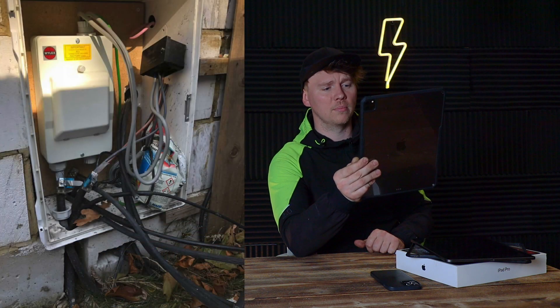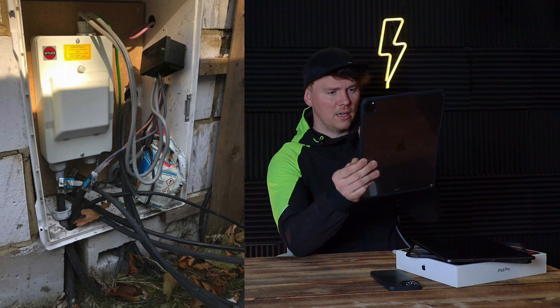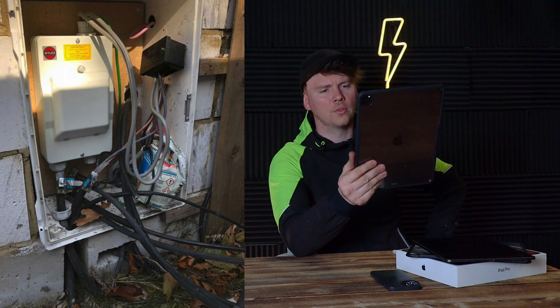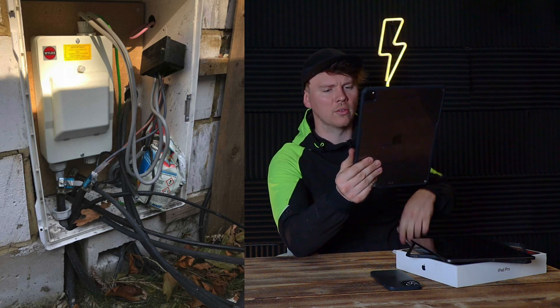Another picture from James: there's a tail gland inside an outside meter cupboard with no lid on, a Henley block floating around, armoured cable that hasn't been glanded correctly going straight into a Henley block off the main tails, and the earth of the armoured has had an earth tag put around it — which I've seen quite a few times. There's no organisation to the cable entry. And for good measure, is that a bag of grout in there as well, just to support the cable? Good job.